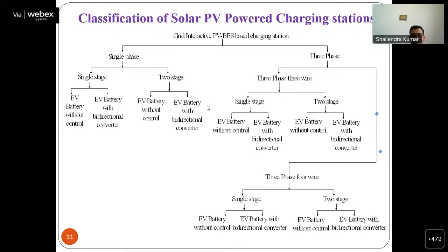In two stage, we can put the boost converter, but in single stage, all power extraction from the PV array is done by the bidirectional converter itself. So there are two functions achieved from this bidirectional converter: extracting maximum power from the PV array, operating as an MPPT unit, and also controlling the battery's charging and discharging current.